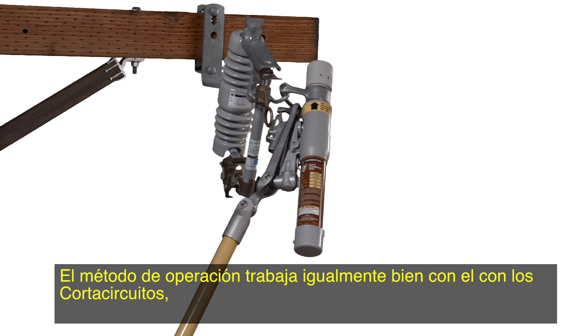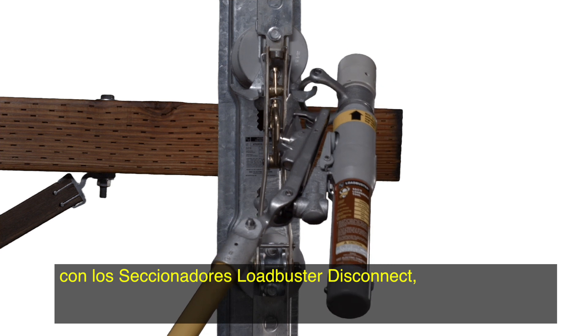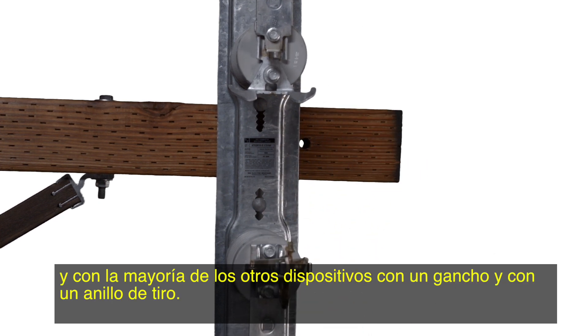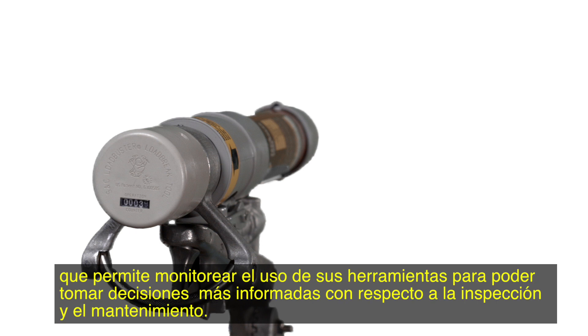The method of operation works equally well with cutouts, Loadbuster disconnect switches, and most other devices with a hook and pull ring. Loadbuster tools manufactured after March 2003 are equipped with a non-resettable operation counter that lets you monitor the use of your tools to make more informed decisions with regard to inspection and maintenance. The operation counter is built into the Loadbuster tool's silencer and can be easily added to existing tools. If you have any questions about the Loadbuster tool, visit our website at sandc.com.